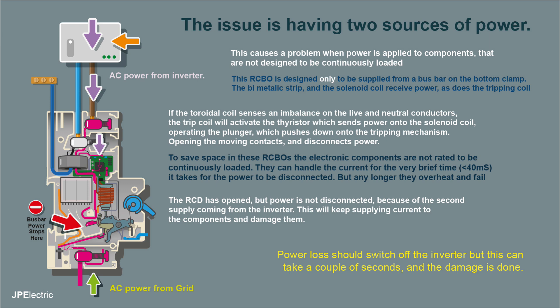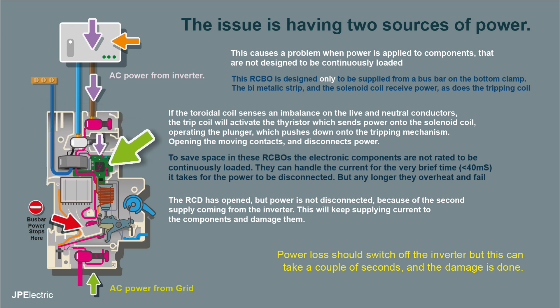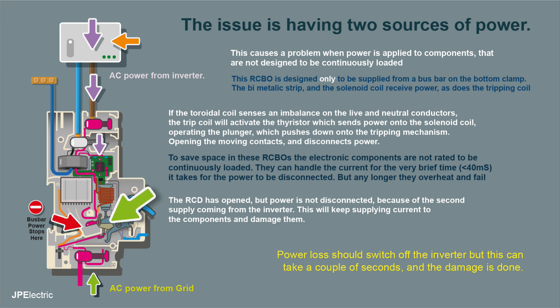Let's have a quick look at how the RCBO works. If the toroid coil senses an imbalance on the live and neutral, the trip coil will activate the thyristor, which sends power onto the solenoid coil, operating the little plunger, which pushes down on the tripping mechanism, opening the moving contact and disconnecting power.